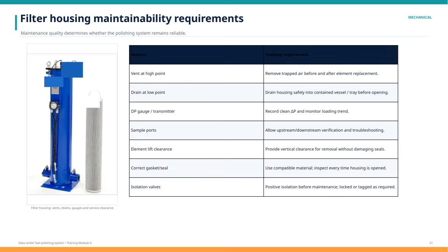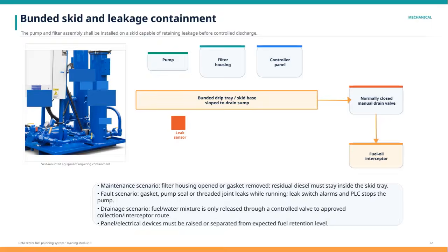Finally, isolation valves must provide positive isolation before maintenance begins and should be securely locked or tagged as required to ensure safety during service. Understanding and following these detailed maintainability requirements helps us keep our fuel polishing system running smoothly and reliably. Here, we focus on the concept of bunded skid and leakage containment for pump and filter assemblies.